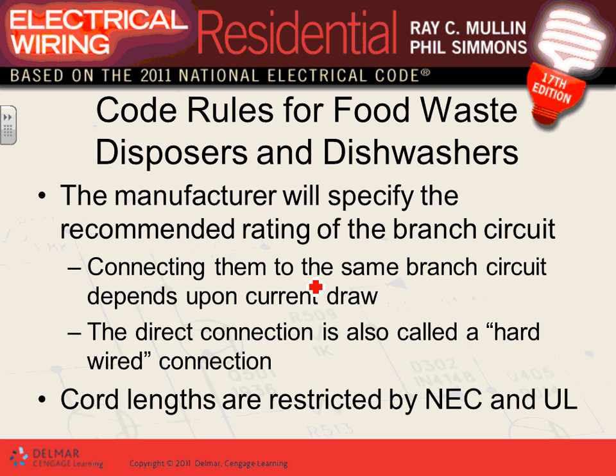A lot of these appliances, guys, here's what the NEC code book tells you. All these appliances will come with a recommendation from the manufacturer. When you go to them, the manufacturer will say the recommendation is a 20 amp dedicated circuit. So you use it. If you don't know, then you use the NEC code book, Article 420, Article 422. Article 422 tells you 13.3 amps or less, 20 amp. Higher than that, you start using a 1.5 multiplier. Always pay attention to the recommendation from the manufacturer.